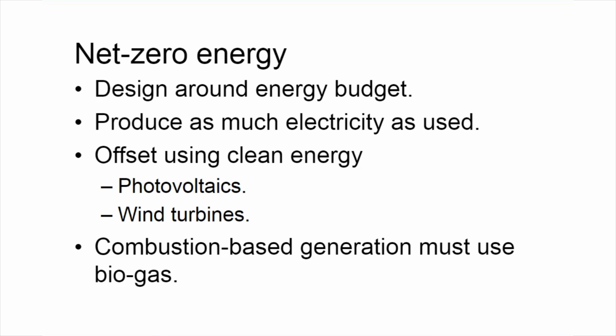Some areas it may be wind turbines versus photovoltaics, but it's really about seeing what's best for your climate, your site, most viable, and trying to design within that constraint. Now, you can use some combustion-based generation sources, combined heat and power, which we'll go into a little bit later in the slides. But in order for that to truly be net zero, you really have to be firing those with something that you've produced. You can't fire it with just straight natural gas or something like that and really consider your building to be net zero. So at that point, you would need something larger scale, an anaerobic digester producing biogas that then you could use to run through a combined heat and power system or even possibly a fuel cell to produce that electricity.